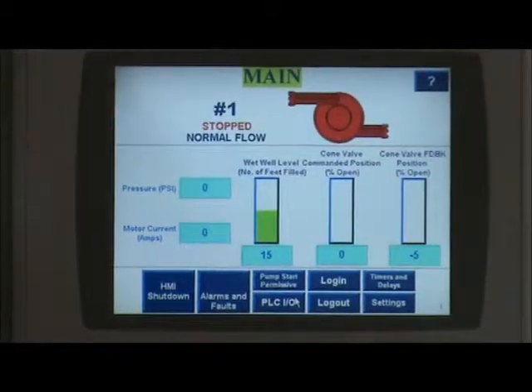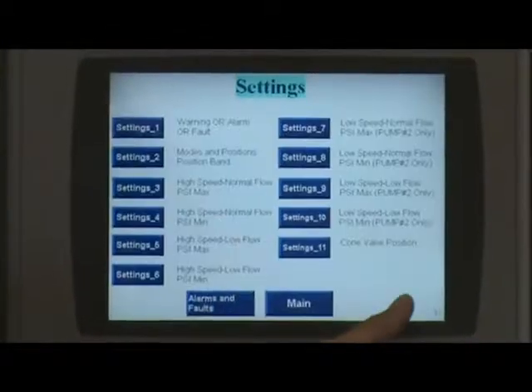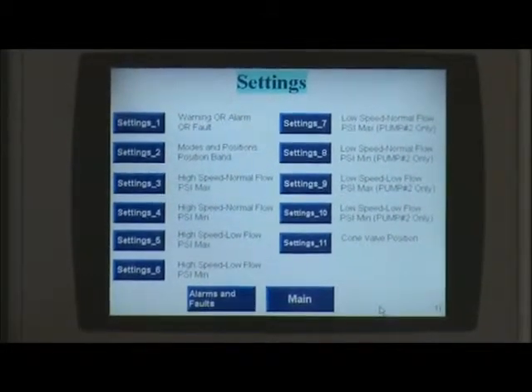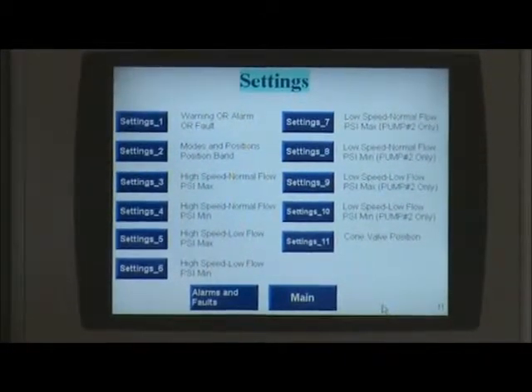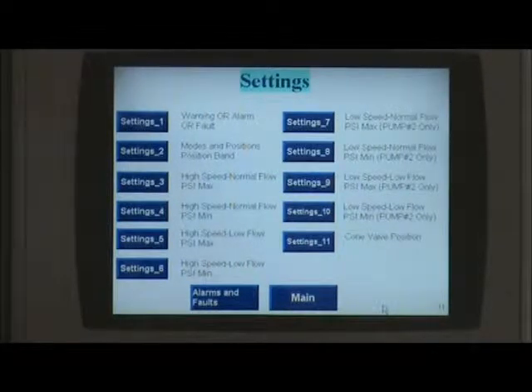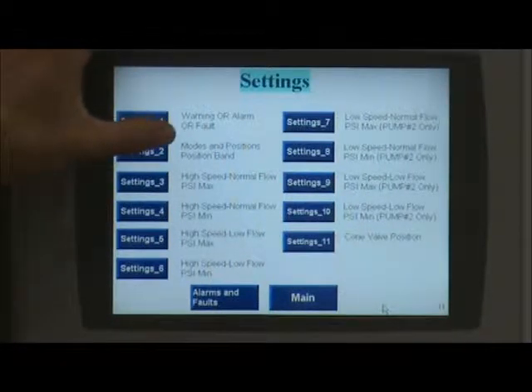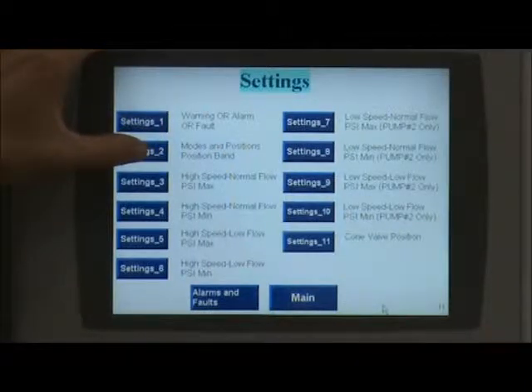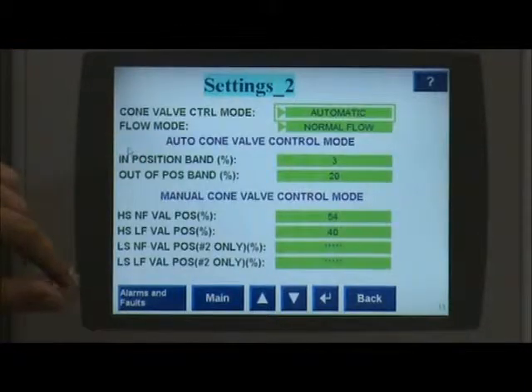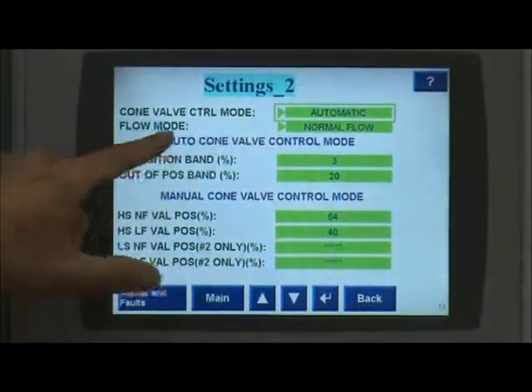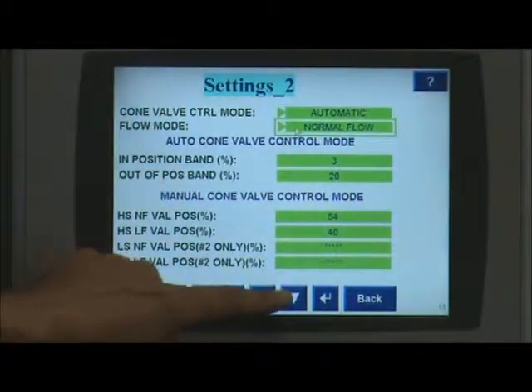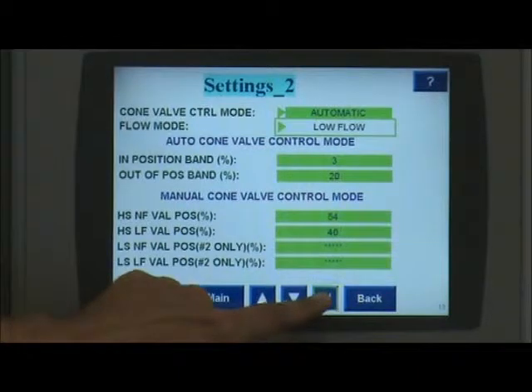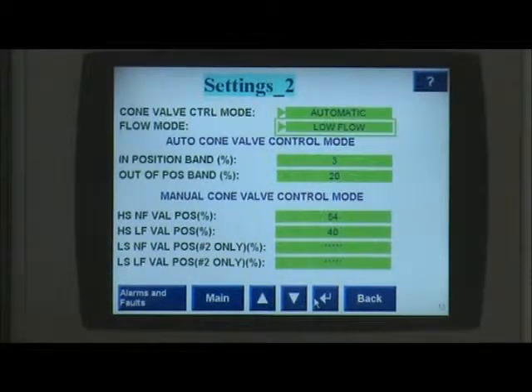The last navigation key is the settings. Everything in here affects the operation of the pump and our flow sequencing. This is done at the engineering level and should be coordinated with the on-site engineer. I'm going to give an example of changing between the low and normal flow modes. So you go into settings 2, click on the normal flow, click the down arrow to go into low, and then enter. And now we're in low flow mode.